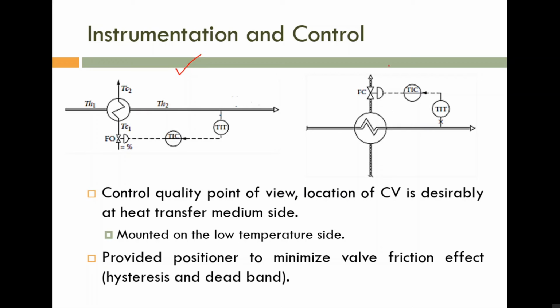Please note what I said is applicable only for liquid to liquid heat exchangers. For steam heaters and the remaining heat exchangers, this is different. For a liquid to liquid heat exchanger, please note we are manipulating the heat transfer medium at a relatively small temperature, and it is for improving the control quality. In order to improve the control quality, we are manipulating at the relatively small temperature point. Now, the type of control valve and control mode.